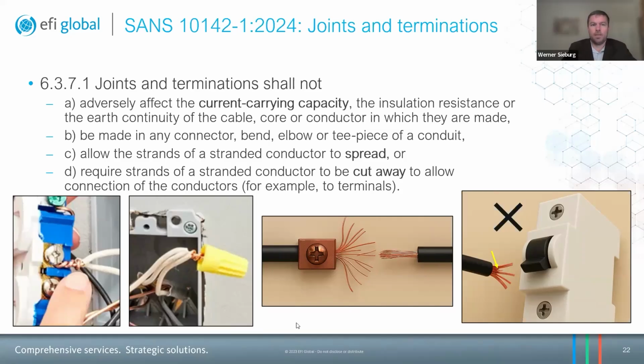And then number D, it must not require the strands of a stranded conductor to be cut away to allow the connection of the conductors, for example, to terminals. So on the right-hand side, we've got a terminal. I'm not sure if it's visible on the picture, but some of the conductor strands were cut away. Otherwise, there would not have been sufficient space to insert it into the circuit breaker or the switch.